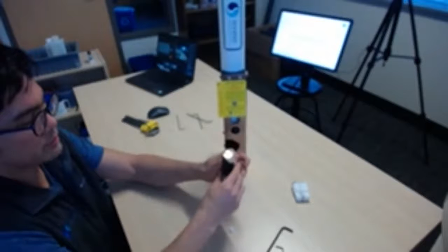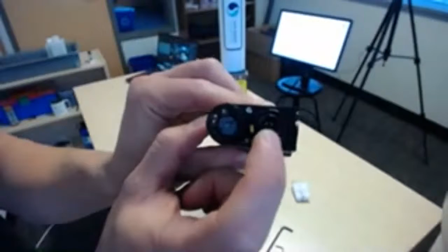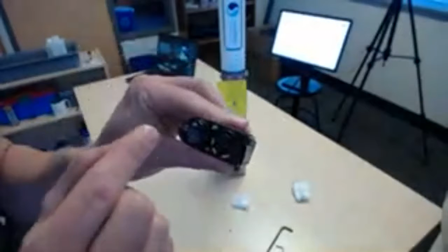Now, before I install, I like to just take a look at my sensor. I'll hold this up to the camera. So we have our sensing elements on this side, and we have our connector here, which is protected by this O-ring right here. I'm just looking for any kind of debris that could be bridging this O-ring that might compromise the seal. This one looks pretty good to me, and I'm looking to make sure that there's not any of this KCl solution on any of these pins. These pins look pretty dry, so I think that this one is ready to go. Okay, now I'm just going to install this into the slot where I removed the dummy plug. I'm going to put it in, line it up, push it in until I can feel the connector go into the HydroCAT EP. And then I'm going to slowly tighten these, again, doing them a little bit at a time, alternating between each one.